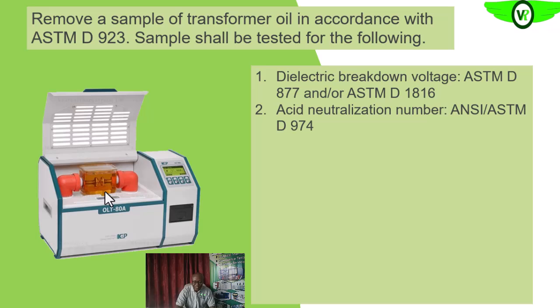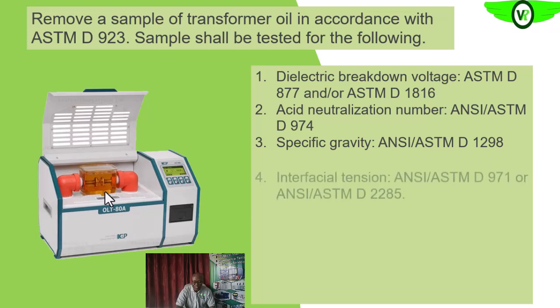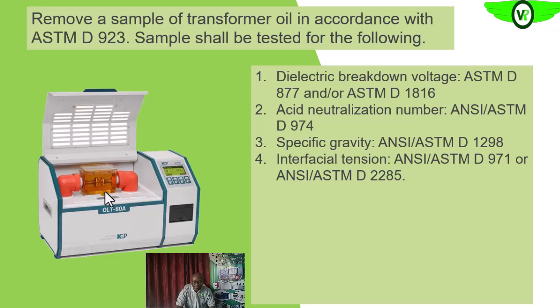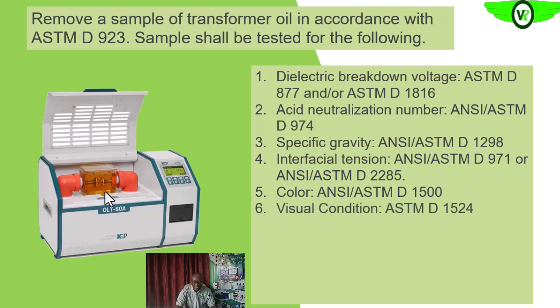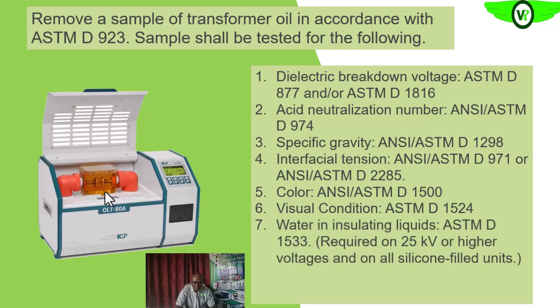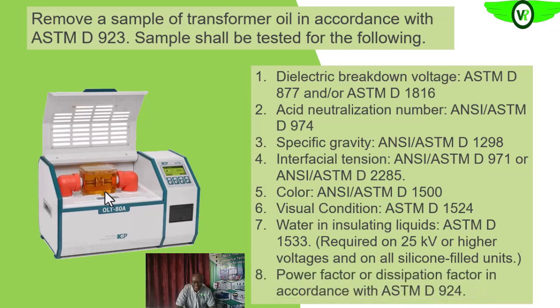The acid neutralization test, to get the acid number, we'll carry out the test. They will test the specific gravity of the oil. Of course, we know that the specific gravity will affect the viscosity of the oil and thus the cooling effect of the oil, and also even the dielectric strength of the oil. Interfacial tension, we check it, and then the color, we also look at it. Then the condition visually of the oil, we'll look at it. Then the amount of water that is contained in the oil, we also check it, and then the dissipation factor of the oil, we also check it.